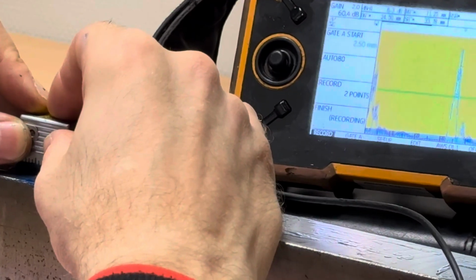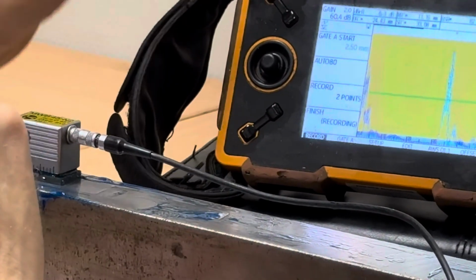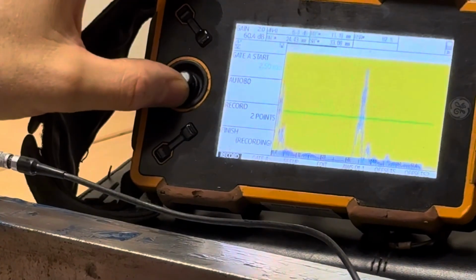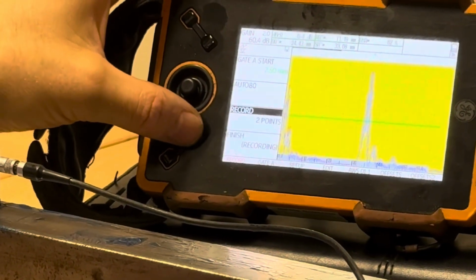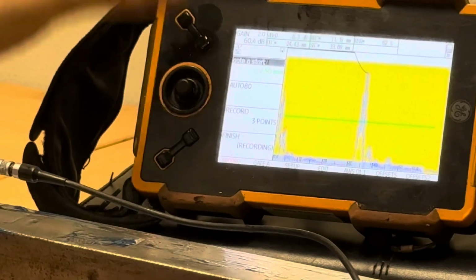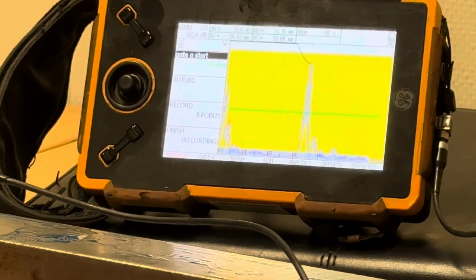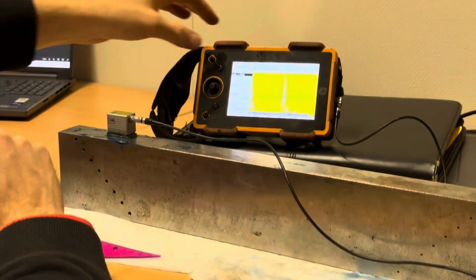We do this for all these points. We hit this point, so once again, we check the amplitude maximum. The envelope helps us with this. Next, we go up again and record. With a press, we record it, and so on. We check all these points, and at the last point, we then proceed.